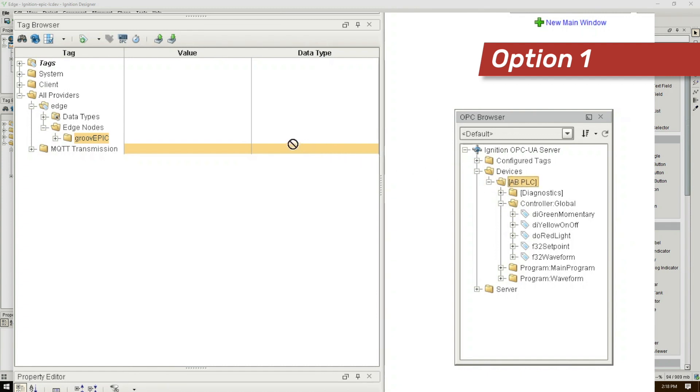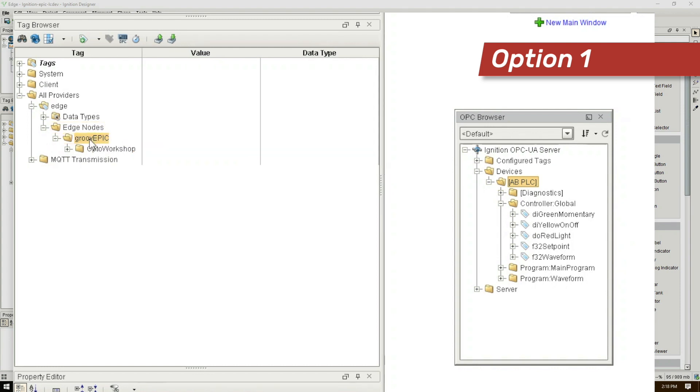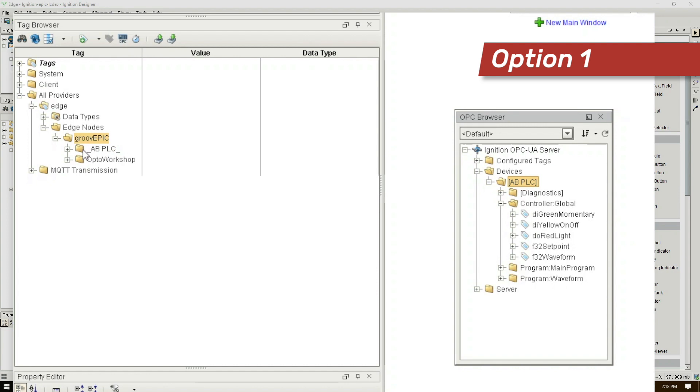Option one we could just click, drag, drop this entire AB PLC device tree over the node ID folder and all of our tags from our PLC including diagnostic tags. This also creates the Device ID folder and populates all of the tags all at the same time. And at this point we'd be done.